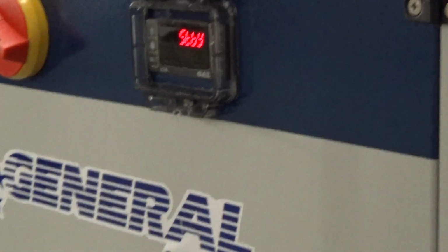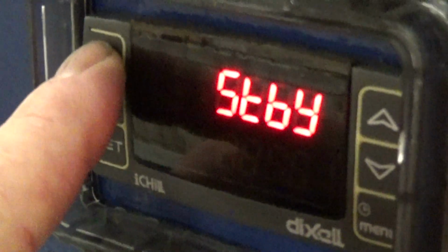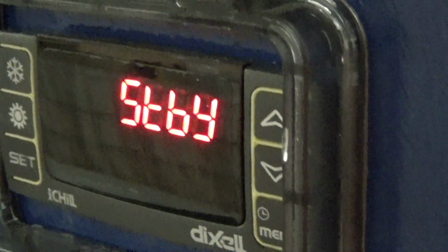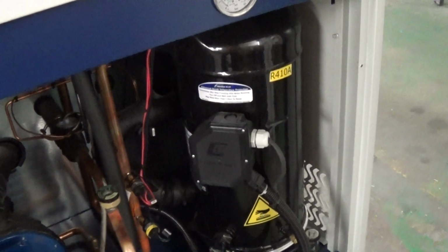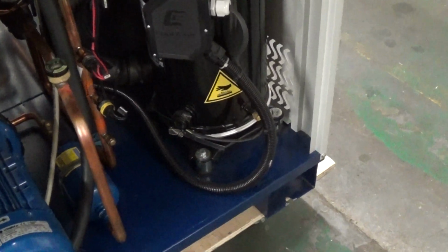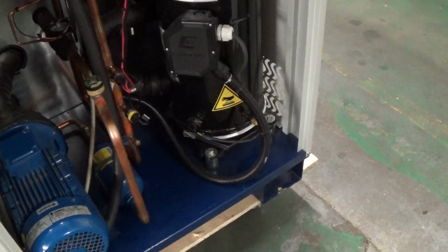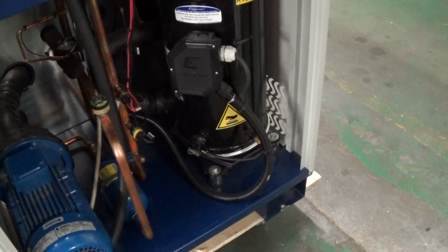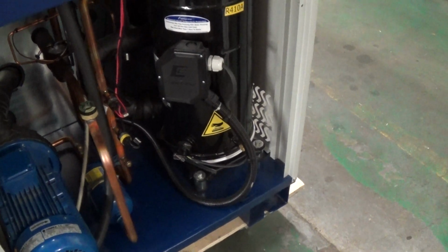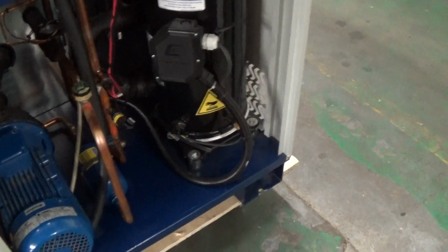When you have this chiller under power or turn it on and off, it's best to do it just by the top left snowflake here, which is the standby button. Right now I do have it in standby, which is effectively off, but the crankcase heater on the 14 horsepower Copeland Scroll compressor will remain on, and that's what you want. Don't turn your chiller on and off by the main disconnect unless you're going to power it down for a very long time. If you do, when you do power the unit back up, let that heater be on for at least 12 hours before you run the compressor.